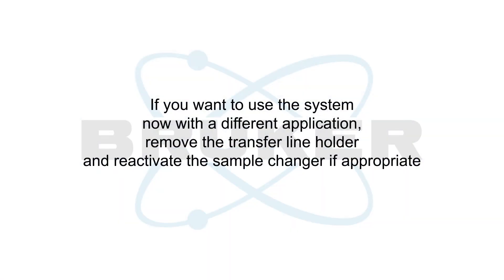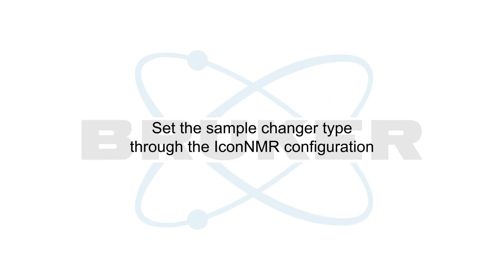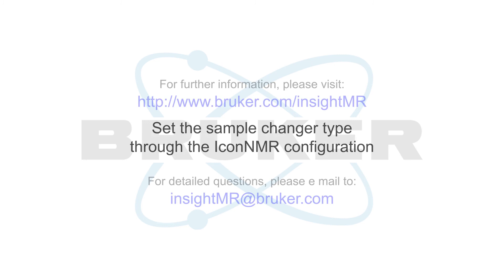If you want to use the NMR system now with a different application, remove the Insight MR transfer line holder and reactivate the sample changer if appropriate, and then set the sample changer type through the ICON NMR configuration.